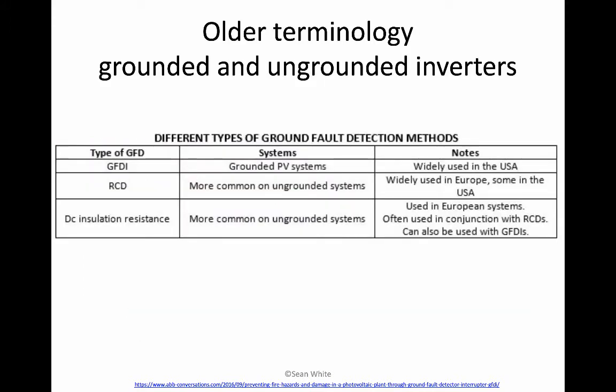Older terminology for grounded and ungrounded inverters. So remember, once again, a grounded inverter, I call it a fuse grounded inverter right now. Both of these we call functionally grounded inverters. And for an ungrounded inverter, we used to call those transformerless inverters, but now the proper term to use is non-isolated inverter.